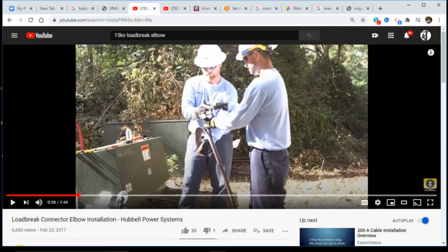I think the biggest things to look out for here is, here's the main thing that people do in error. One, they think the end of the wire is where the elbow needs to go. No, you need to give yourself sufficient ground wire down here, then install your elbow wherever you're going here as far as the measurement is concerned. Does that mean I need to pull extra wire out on both ends?